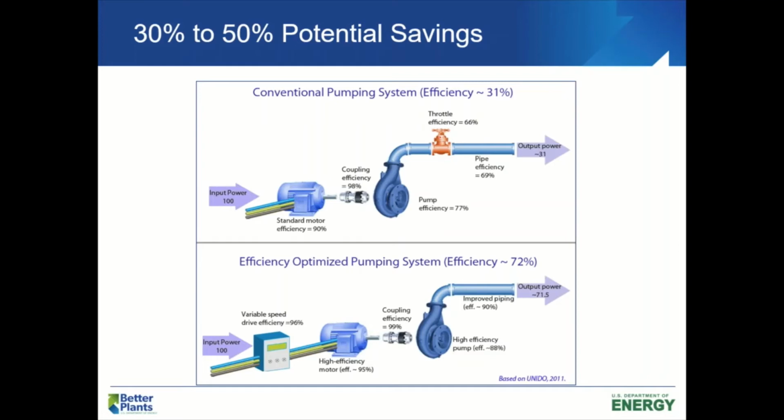Okay, so here's a really good example of what I would call a common pump opportunity, and for most of us in a lot of facilities around the U.S., they're inherently built with the idea of using a throttle valve to control the flow, right? So we have our pump, we have our motor and everything hooked in to our pump. Pump's just pumping fluid. It might be going out to the cooling tower, right? Or it might be going to our process or our chiller. And a lot of these, instead of coupling things with a variable speed drive, we just have a throttling valve, right? And if you were pumping too much, you just crank down on that puppy. Well, what that does is it introduces a lot of pressure drop, right? It's a lot of friction that you have to pump across. And so it's just a really poor form of trying to control our flow rates, okay?